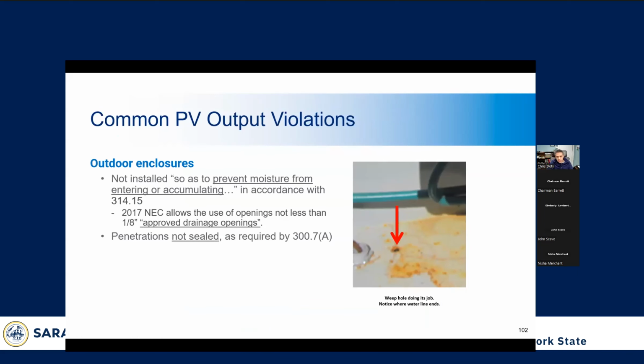Here we can see a problem with enclosures themselves. Code allows for the use of what's called weep holes, which are holes drilled into an enclosure that allow water to exit the enclosure to help avoid pooling. Weep holes are used to prevent moisture from accumulating in the enclosure, as I sort of just said.